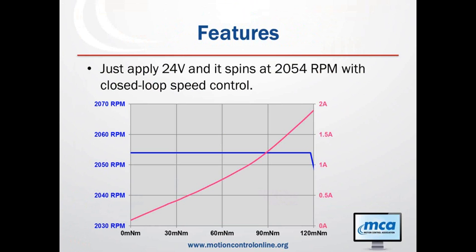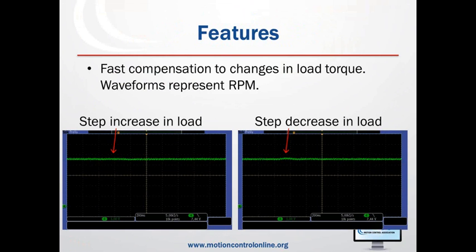These graphs show a response where RPM is plotted as a voltage. I'm doing a step change in the load torque and seeing how well the speed control compensates. Motors have momentum and take a relatively long time to change speed, whereas the electrical feedback happens about 100 times a second, so there's only a very small overshoot visible.